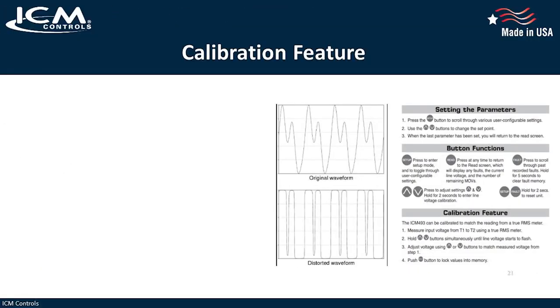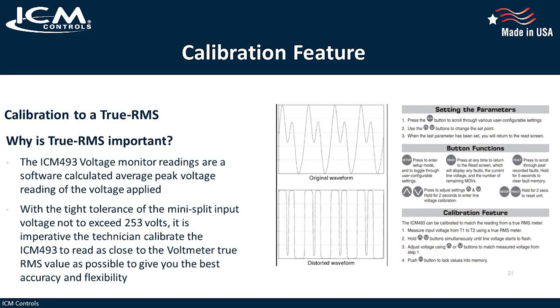Calibration capabilities. The ICM 493 is programmable. It allows for calibration to a true RMS value because mini splits have tight tolerances, with input voltage usually maxing out around 253 volts before the motherboard fries. That's a costly repair, not to mention the customer is left to deal with 90-degree temps without AC. In a lot of regions across the country, the supply power is already coming in high. In the Southwest, for instance, it's not uncommon to get readings that are already close to 250 volts. That means even the slightest transient will blow the motherboard.